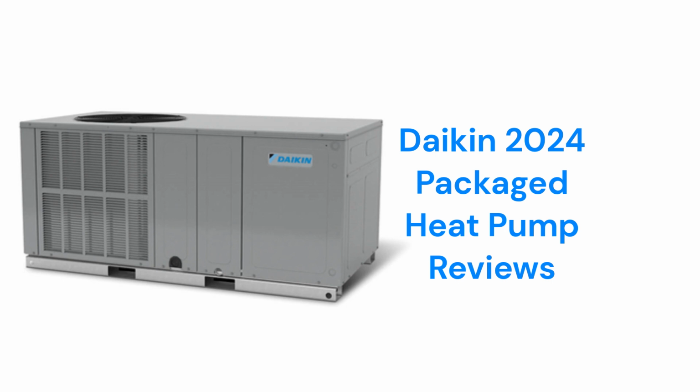They offer optional electric heat kits in sizes from 5 to 20 kilowatts, and the units are backed by a very good warranty, but they are relatively loud in operation with sound levels of up to 80 decibels even though they have compressor sound blankets.